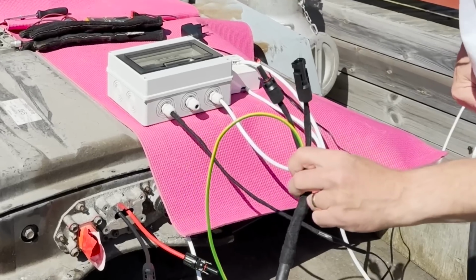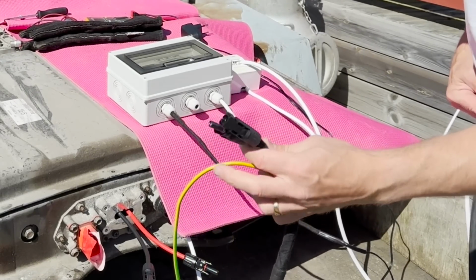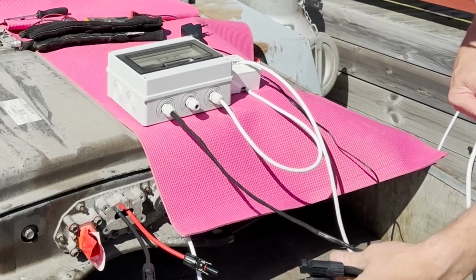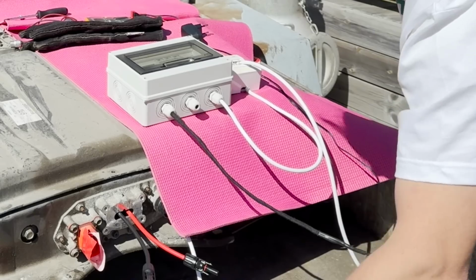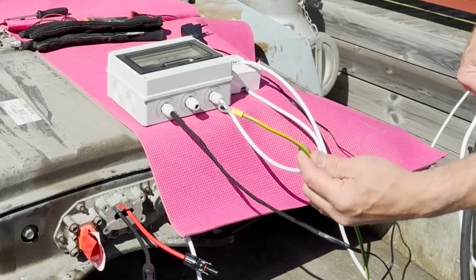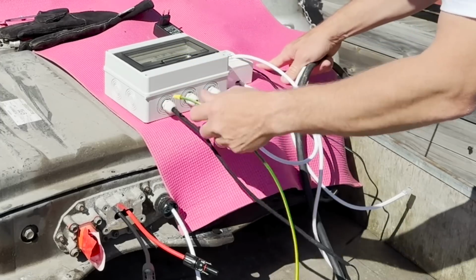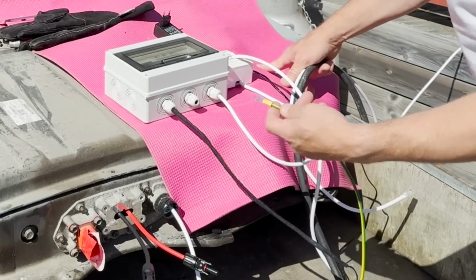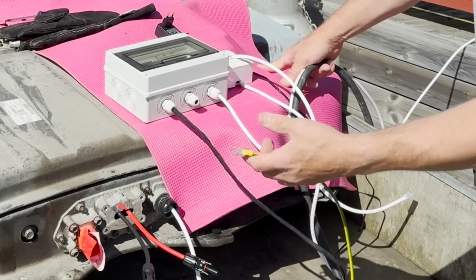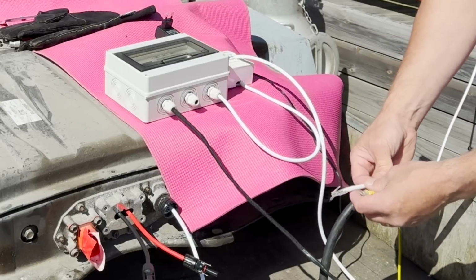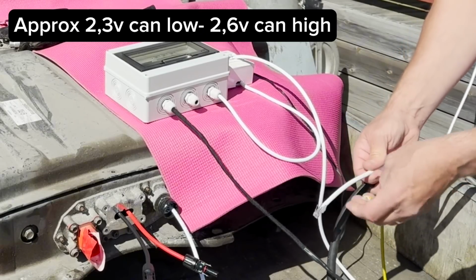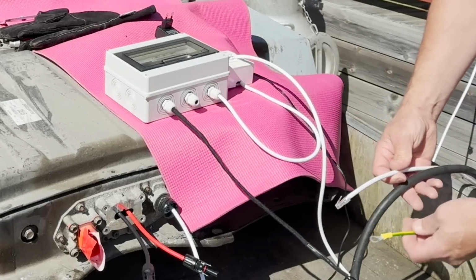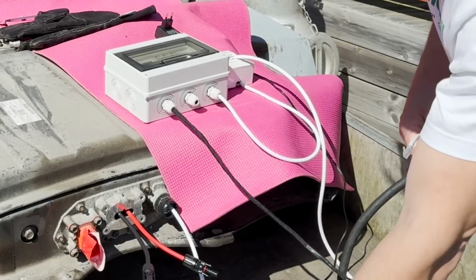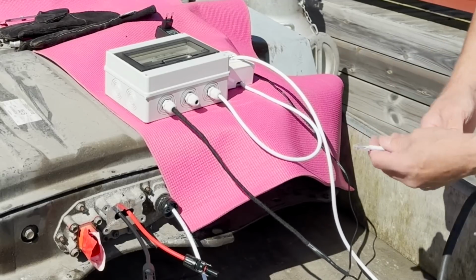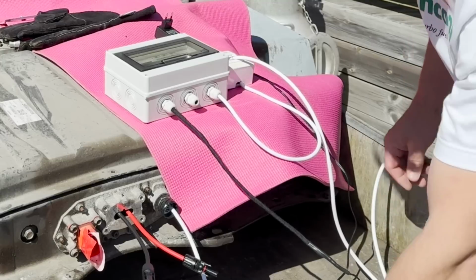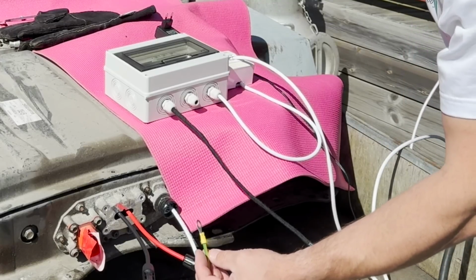This will be connected to the inverter, the high voltage negative and the positive connection that will be connected to the battery. And probably the most important lead here is the ground wiring. It's super important to ground the battery together with the inverter, so we don't have any voltage difference here. So instead of 2.5 volts, we can have a lot higher than that if we don't ground the battery with the same ground as the inverter and the rest of the system. It's super important, because the CAN bus interface can burn up then. So the first thing to do here is to ground the battery.